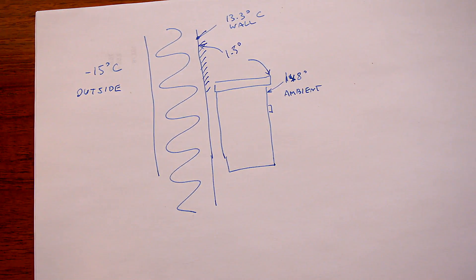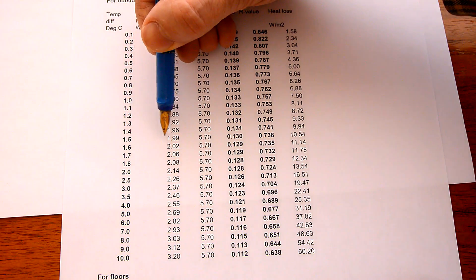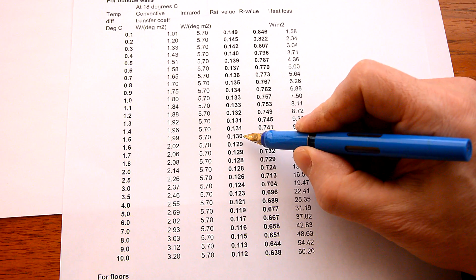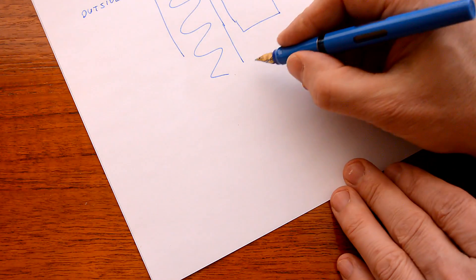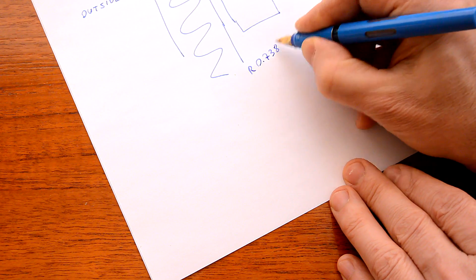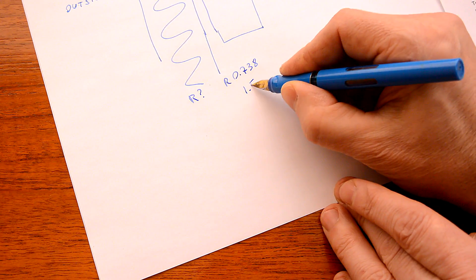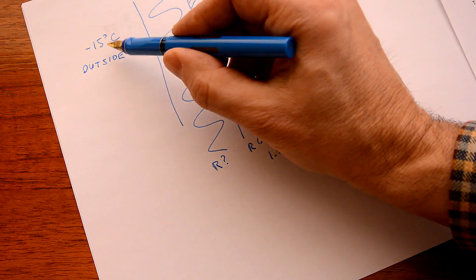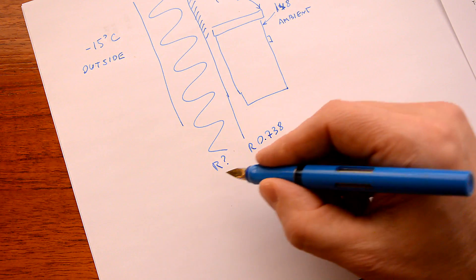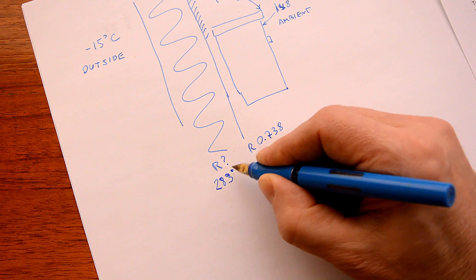That boundary layer also has an R-value. Looking up the R-value for this boundary layer on the spreadsheet I put together — at a 1.5 degree temperature difference, the R-value of the boundary layer is 0.738. We have R 0.738 with a 1.5 degree temperature difference. And through the wall, we're going from 13.3 degrees to minus 15 degrees — about 28.3 degrees temperature difference.